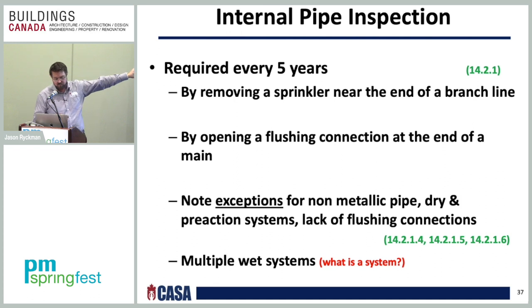As I mentioned, it's required every 5 years. The way you do an internal inspection is by removing a sprinkler near the end of the branch line, or by opening a flushing connection at the end of the main. There are exceptions for non-metallic pipe. For dry and pre-action systems, a lack of flushing connections would be an exception. Also, whenever you have multiple wet systems, the standard allows you to do every other one. So you don't have to do an internal inspection on each and every wet system every 5 years. You can do one after the other.